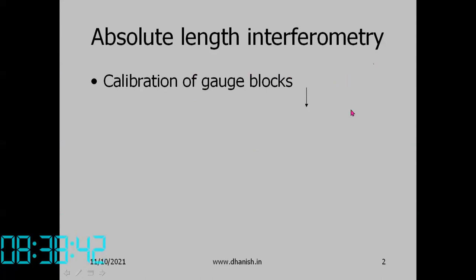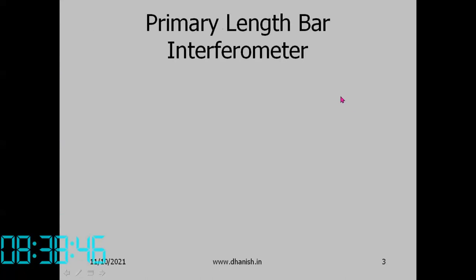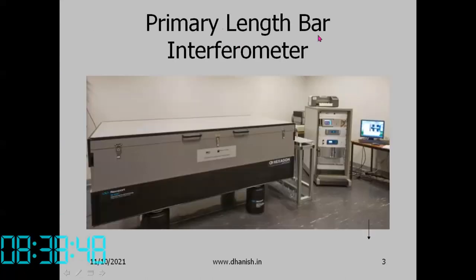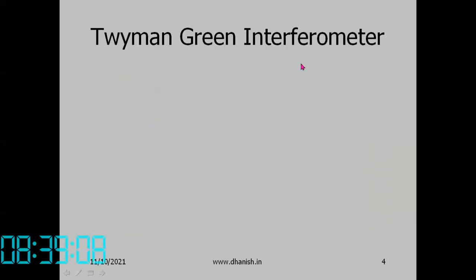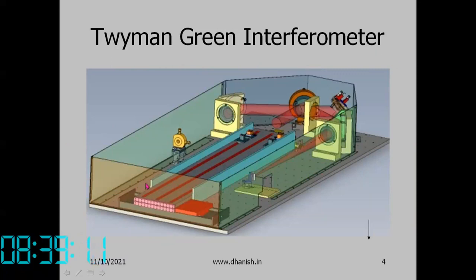Grade K gauge blocks are calibrated using this method. A primary length bar interferometer is used — long gauge blocks are placed inside it. There is a reference gauge block, and interference between the two surfaces is observed through cameras. This is called a Twyman-Green interferometer.